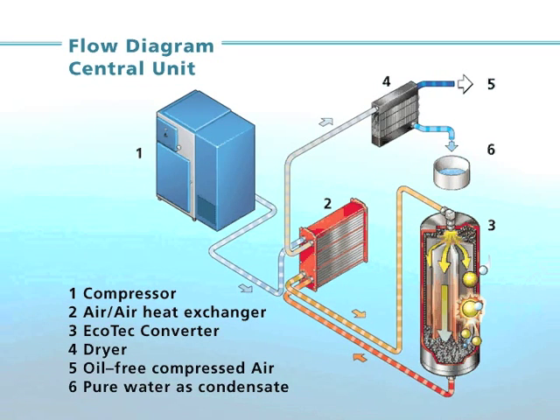The compressed air coming out of the compressor is preheated in the air-air heat exchanger and then flows into the converter, which is filled with catalyst. An electrically operated heater maintains the converter at the proper operating temperature which is required to purify the compressed air.